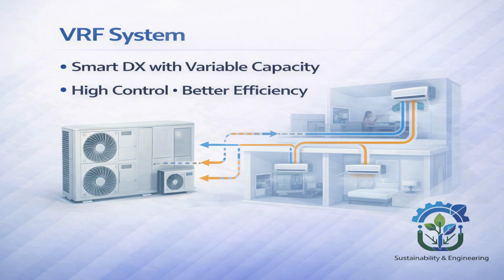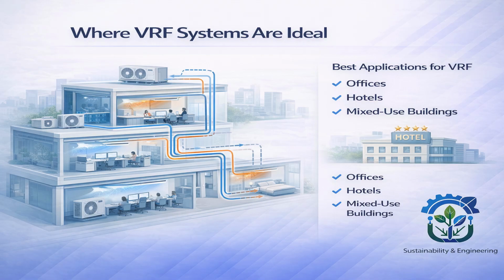be avoided. Now that we understand what a VRF system is, the next logical question is, where does VRF actually make sense? VRF systems perform best in buildings where flexibility and zoning are important. Let's start with office buildings. In offices, different departments operate at different times, meeting rooms have high peak loads, and workstations have lower steady loads. With VRF, each zone can respond independently. A meeting room can cool aggressively, while an adjacent office operates at a much lower load. This is exactly where VRF excels.